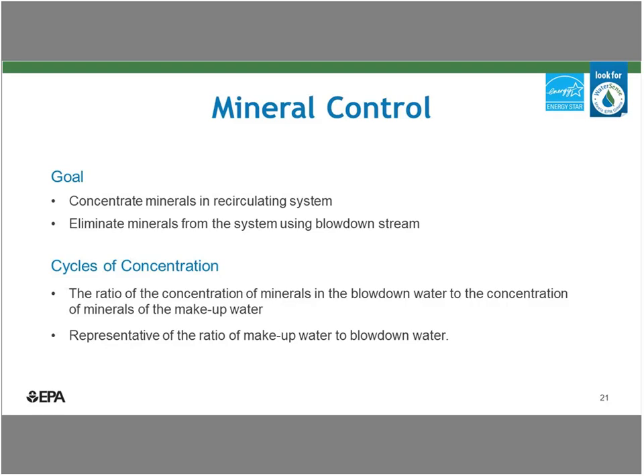If you recall our schematic from the cooling tower, the only water that's added to the system is makeup water. So if you're operating a cooling tower properly, the only significant ways water should leave is through evaporation and blowdown. Drift should be relatively negligible. So reducing cooling tower blowdown is the largest opportunity for water savings.